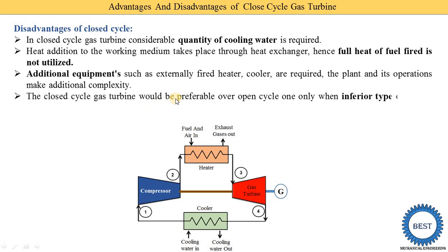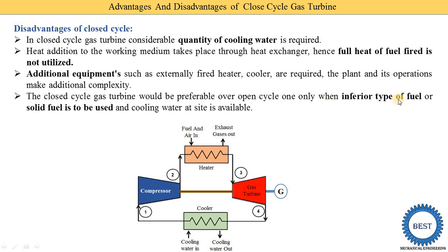The closed cycle gas turbine will be preferable over an open cycle only when an inferior type of fuel or solid fuel is to be used and cooling water is available at the site. We need three conditions to favor using the closed cycle: inferior type of fuel, solid fuel availability, and cooling water availability. When all these conditions are met, a closed cycle gas turbine power plant can be used.